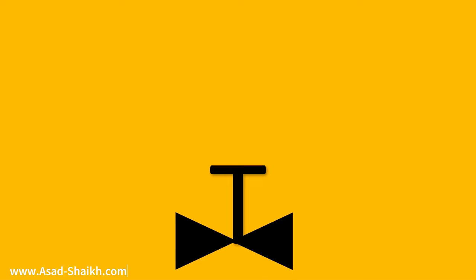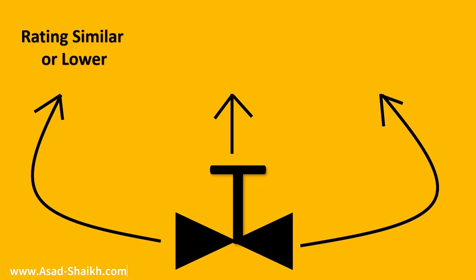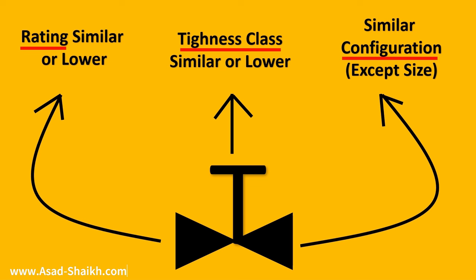Let's summarize type testing. In type testing, if the rating is similar or lower, you can qualify. If the tightness class is similar or lower — generally a similar configuration except the size — then once a particular type is tested, the rest of that type can pass through type testing.